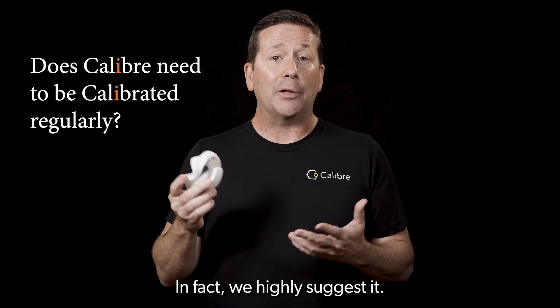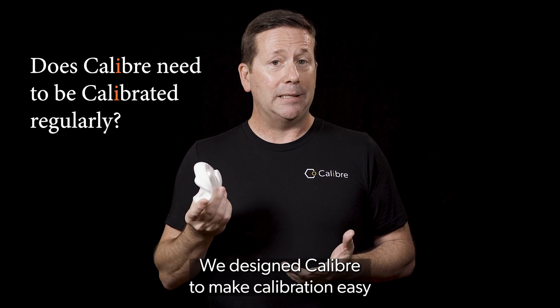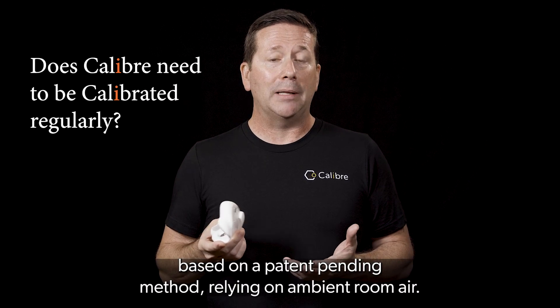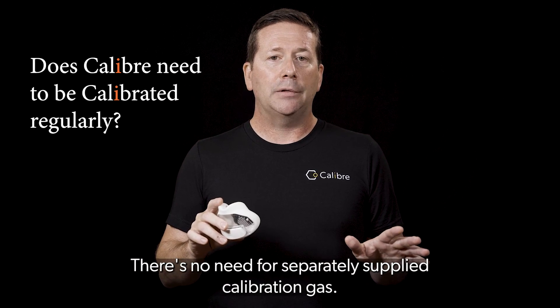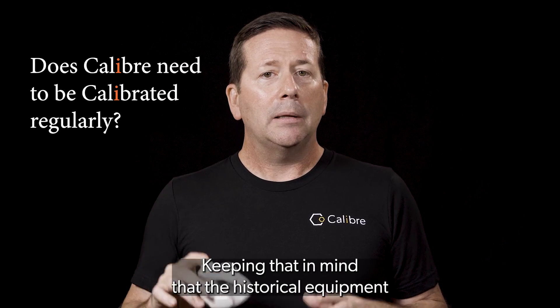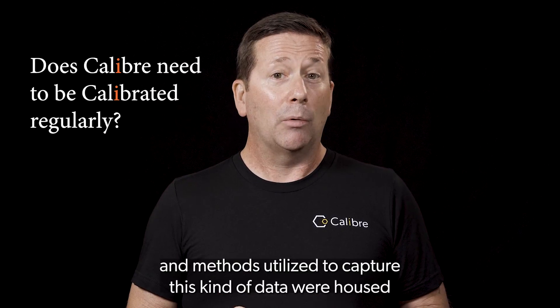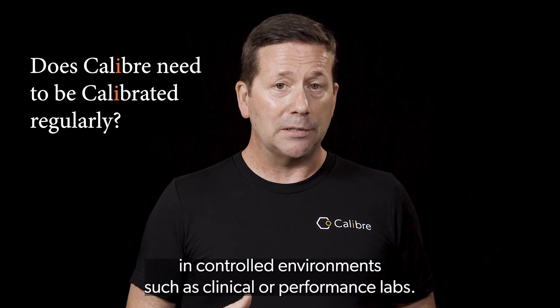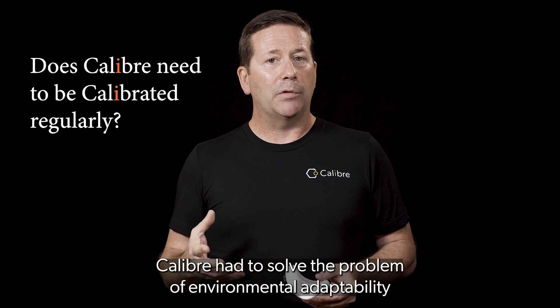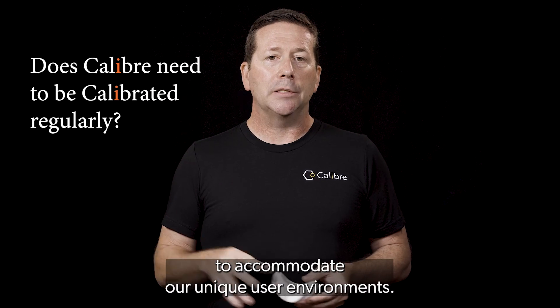The short answer is yes — we highly suggest it. We designed Calibre to make calibration easy based on a patent-pending method relying on ambient room air. There's no need for separately supplied calibration gas. Keeping in mind that the historical equipment and methods utilized to capture this kind of data were housed in controlled environments such as clinical or performance labs, Calibre had to solve the problem of environmental adaptability to accommodate our unique user environments.